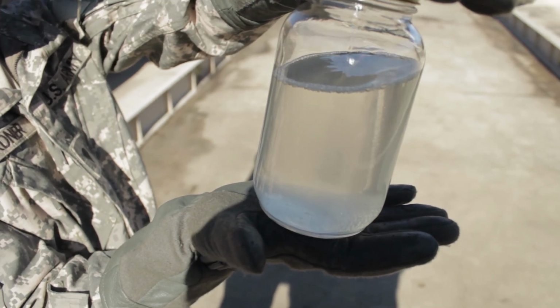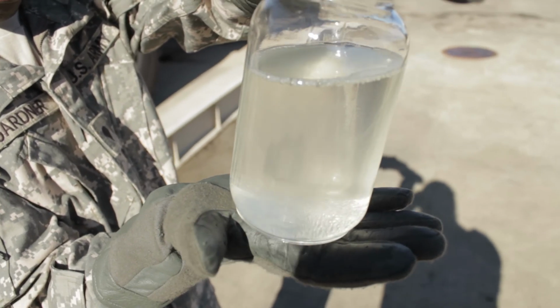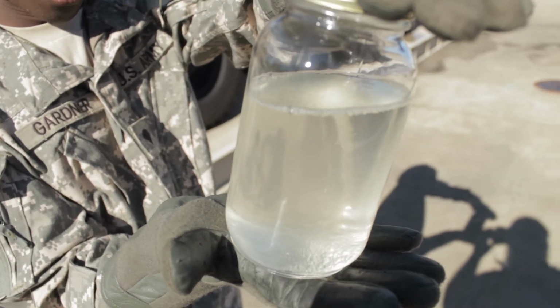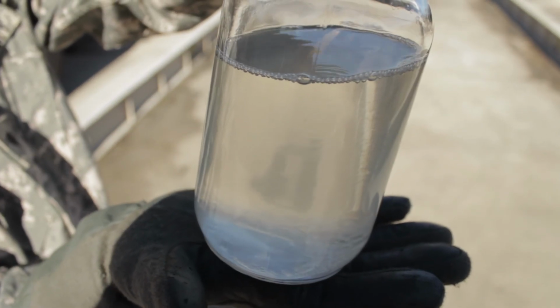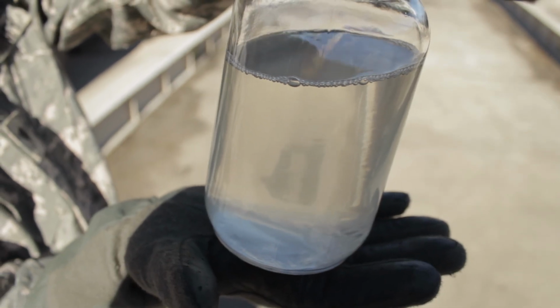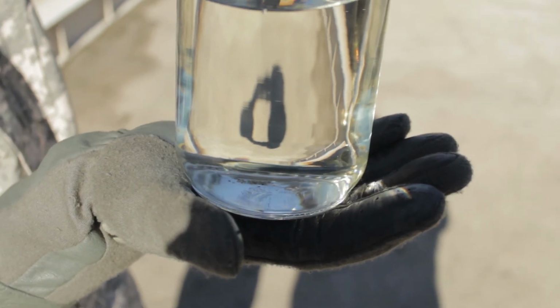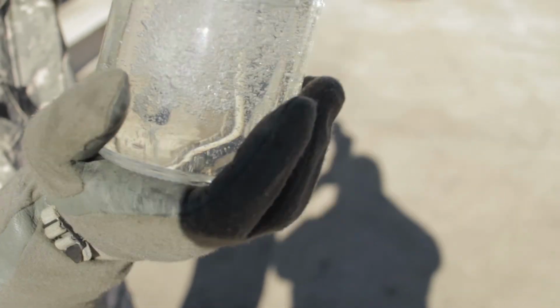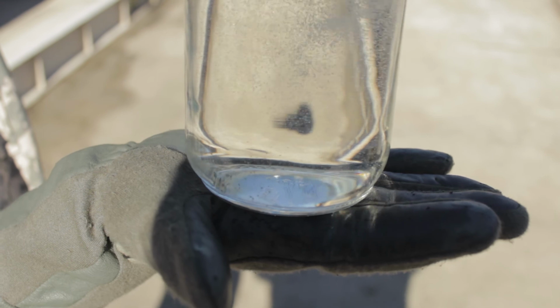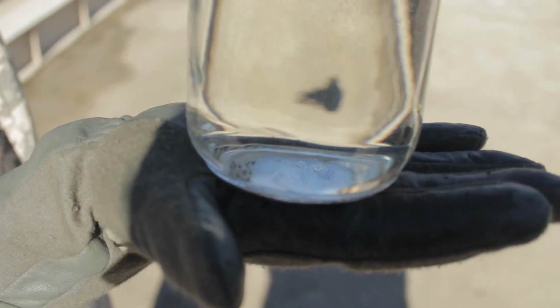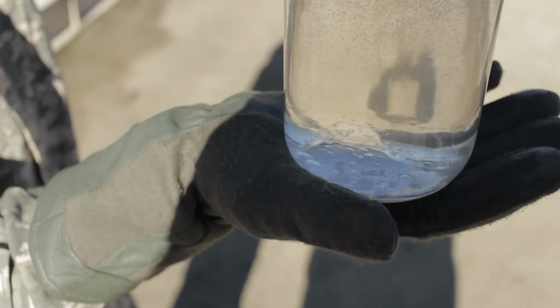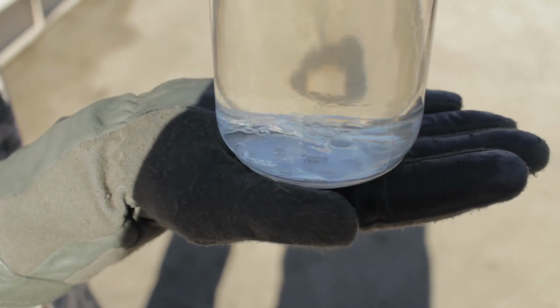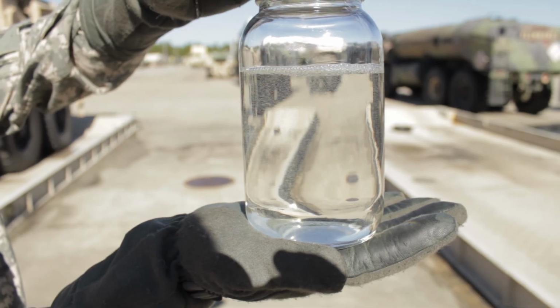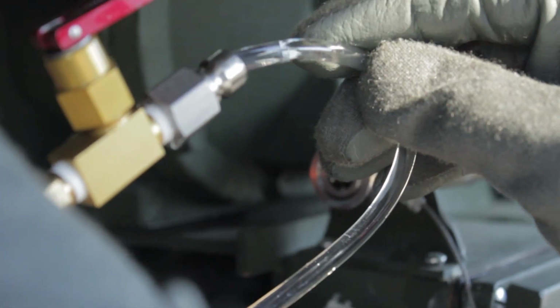If fuel is cloudy, this could be an indication of undissolved water or fine particulate and may require submission of a 1-gallon fuel sample to a local laboratory for further analysis. Swirl the contents in order to create a vortex. Observe the bottom of the vortex looking for water or sediment. Water and sediment are heavier than fuel and will be visible toward the bottom of the vortex. Record the results of the visual examination. If the fuel is clear and bright, empty the clear glass container into the equipment fuel tank or waste container. Uncouple the test probe and unscrew the 2 halves.